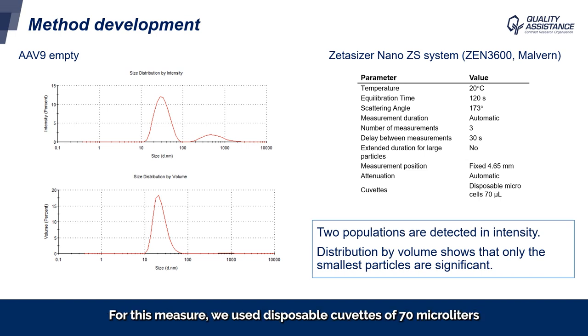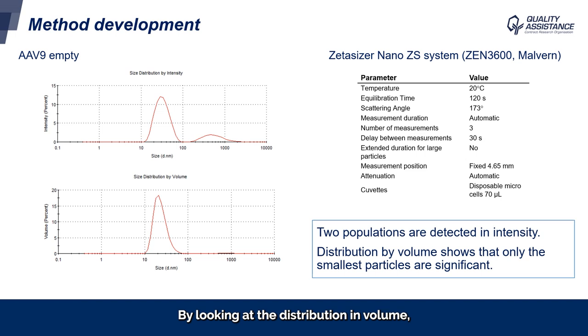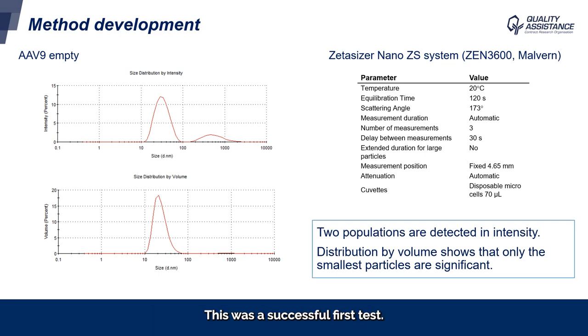For this measurement, we used disposable cuvettes of 70 µL, and the results by intensity show two populations: a first population around 30 nanometers corresponding to the expected size, and a second one around 500 nanometers. By looking at the distribution in volume, we see that the presence of the large population is not significant. This was a successful first test.